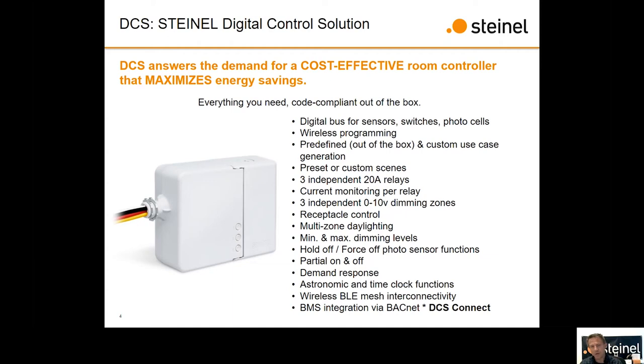The astronomic time clock, very, very cool. During commissioning, we'll take your location from your device and it'll load the dusk dawn tables for your location. So you can control outdoor lighting. You can either brighten up as it gets dark out, or brighten up as the sun comes up, or turn on as the sun goes down. So you've got options there, and integrated time clock function.